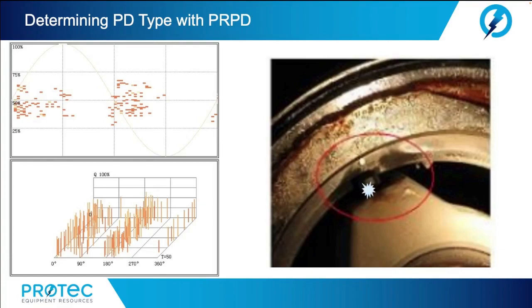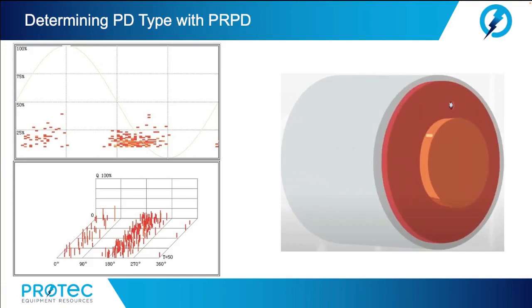The UHF signal is very high and consistent in amplitude. The signal spreads across a wide portion of the half cycle for both positive and negative half cycles. Here we see an example of a void discharge. The UHF emission is lower in amplitude than a floating electrode. The distribution of pulses is less dense than surface or floating discharges. The pulses span a wide portion of both positive and negative half cycles.